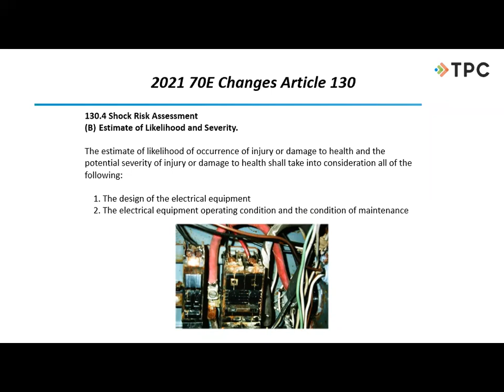The shock risk assessment and the estimate of severity that it might be. They gave us a couple things that we have to look at now in a little bit more detail. The design of the equipment and the condition of maintenance. And condition of maintenance is extremely important. So if we're doing a risk assessment and we're going to try to estimate the likelihood that I might get injured, and I see equipment like this, my estimate's going to go quite a bit higher because condition of maintenance, it looks like that equipment was never maintained. But we do have to take into consideration condition of maintenance for not just shock risk assessments, but also arc flash. We have to look at the condition of maintenance of that equipment.